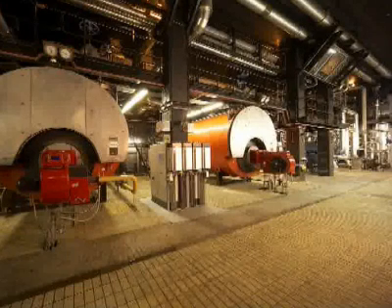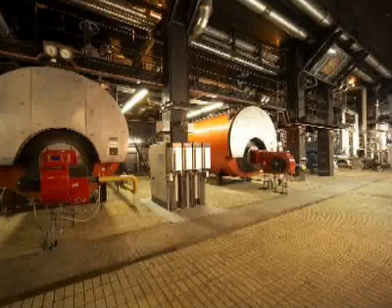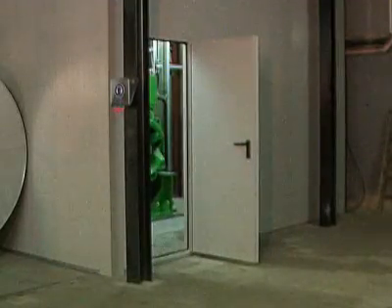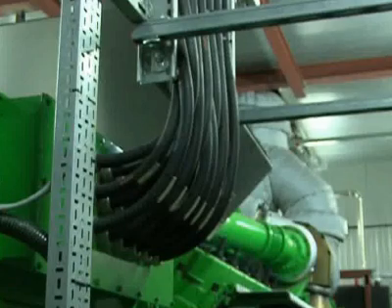This is the refurbished energy center as it looks today, with the two remaining refurbished boilers on the left providing a backup for the new tri-generation system on the far right. The combined heat and power engine, or CHP, is housed in a soundproofed enclosure directly beneath the museum's library, generating 1,800 kilowatts of electricity, with a generating efficiency of 42% and 44% for heat.